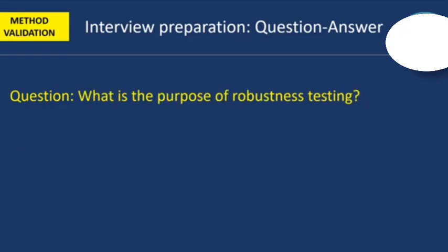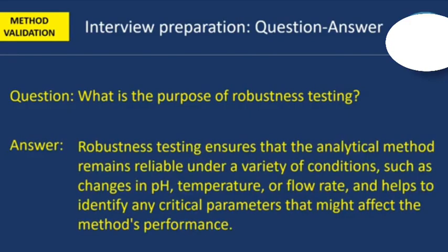Next question. What is the purpose of robustness testing? Robustness testing ensures that the analytical method remains reliable under a variety of conditions such as changes in pH, temperature, and flow rate, and helps to identify any critical parameters that might affect the method's performance.